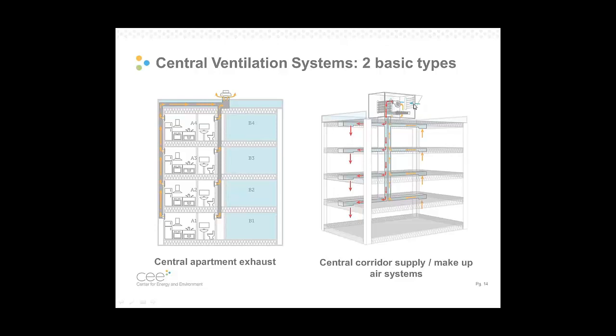But they're commonly ducted to one fan. So that's the critical detail, is that there's multiple inlets on a singular fan. On the supply side, outdoor air is typically brought in and conditioned. This one happens to be on the rooftop. So the air is conditioned and delivered to typically the hallways in the apartment building. Hallways and common areas are what's typically served with a supply system.